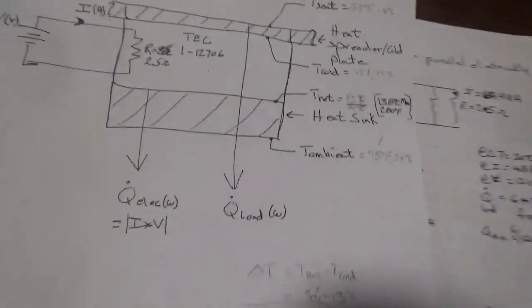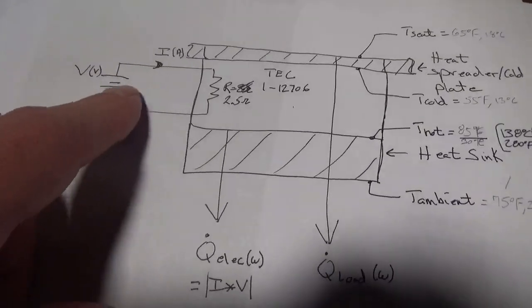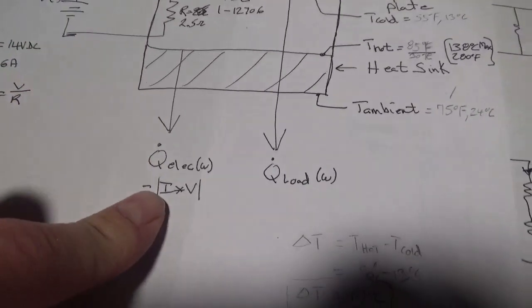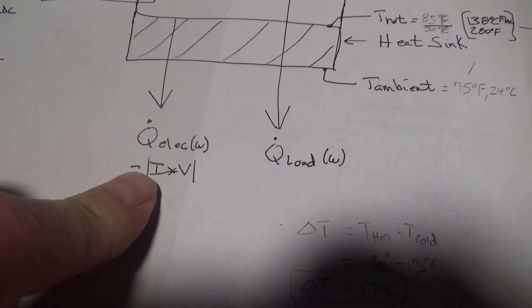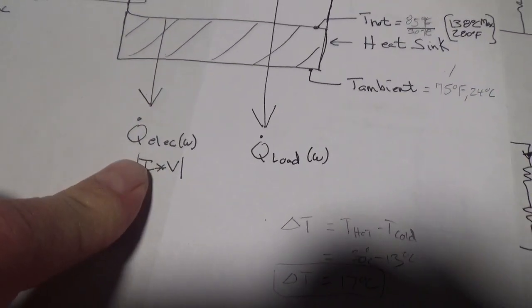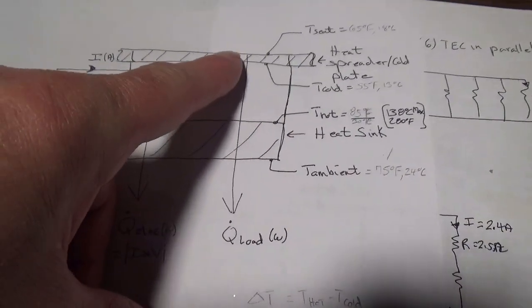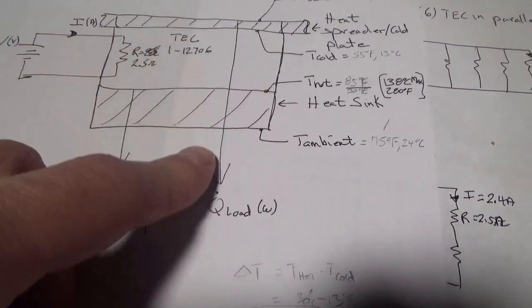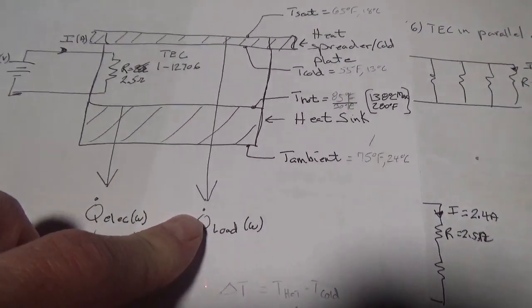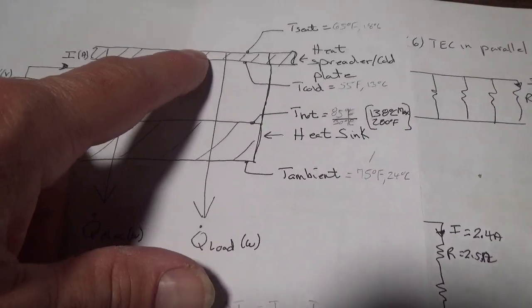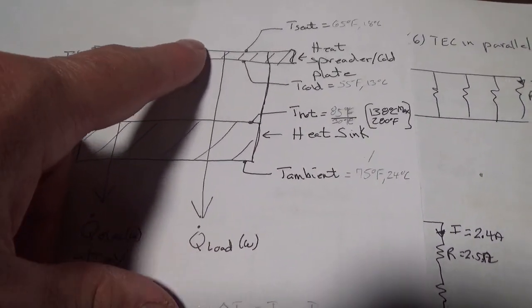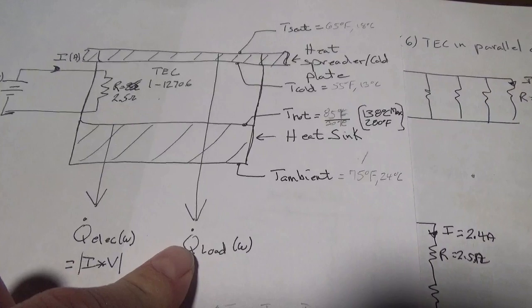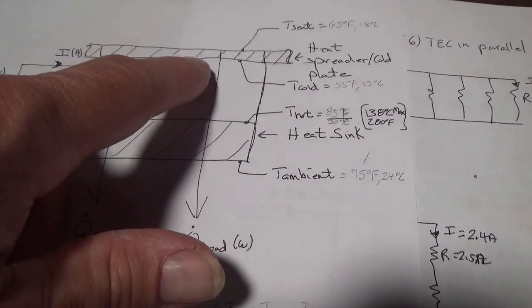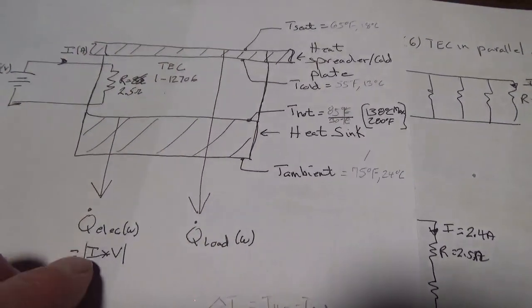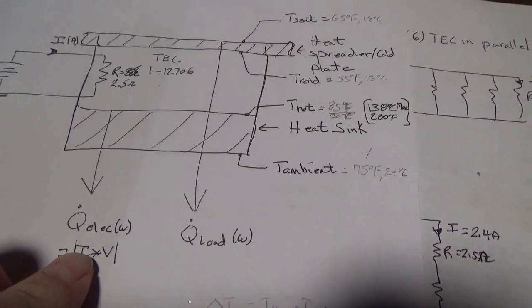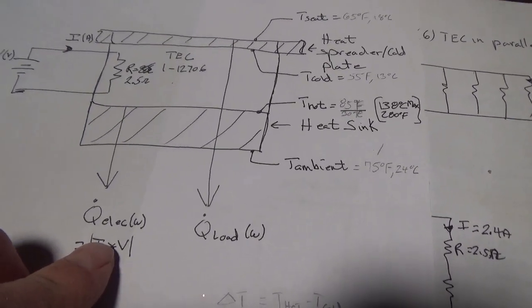So this says 12 volts, 30 amps. We have to get rid of 345 watts of power, and we can pull 210 watts off of that cold plate. So you could put a 210 watt light bulb on that cold plate, and it should be able to pull all 210 watts and keep that at 65 degrees. We also have to get rid of this extra 345 watts of heat power.